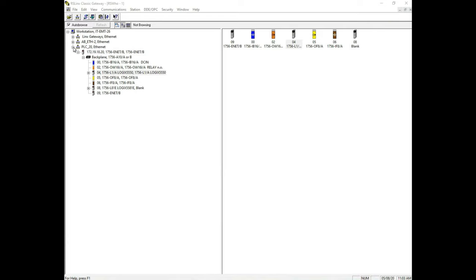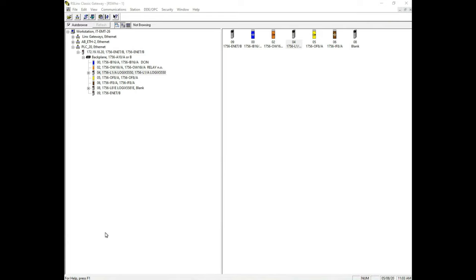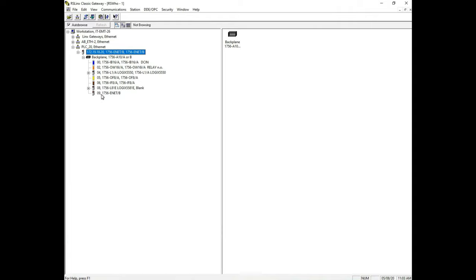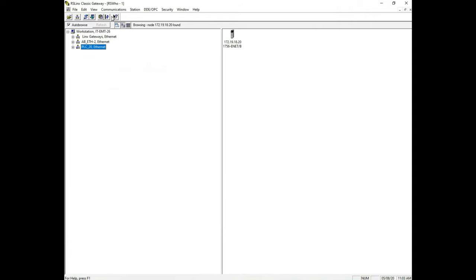Now we've established communications with our PLC 20 rack. What I want to do next is establish an Ethernet IP. The difference between Ethernet and Ethernet IP is Ethernet is only going to look at that one card in that one rack. Within that rack, I've actually got two communication cards. So we're going to see PLC 20 again. The older network card is address 20. The newer network card is address 21, but you're going to see these exact same cards in that slot.